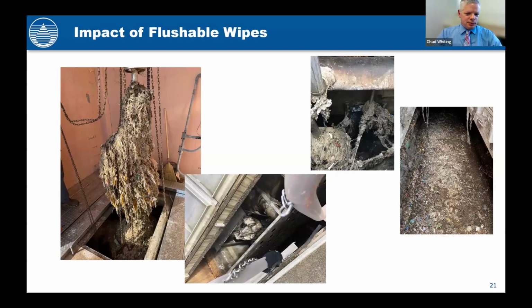So now I'll go into talking about the not so flushable wipes. In our plant, we have scum wells with mixers in them. This picture on the left is a scum well mixer just inundated with rags and inoperable, tripping out, burning out motors, a lot of maintenance headaches. We spend over $1.5 million a year on maintenance for dealing with these flushable wipes. This is a primary clarifier gate where the flow comes into the tank, almost totally blocked with the rags and other channel issues that we see with floatables and flushable wipes.